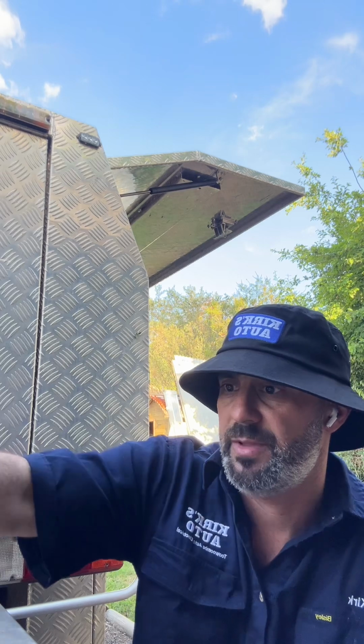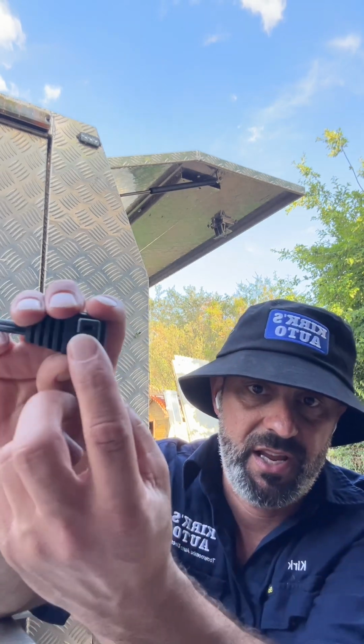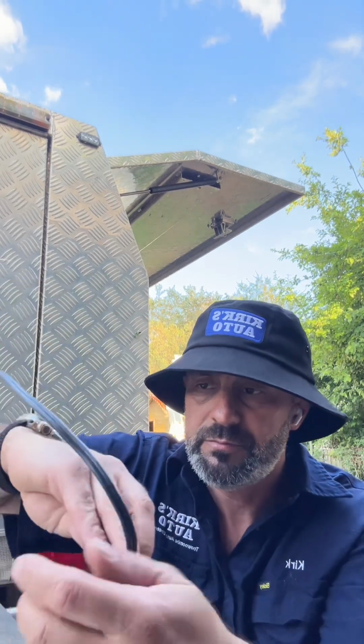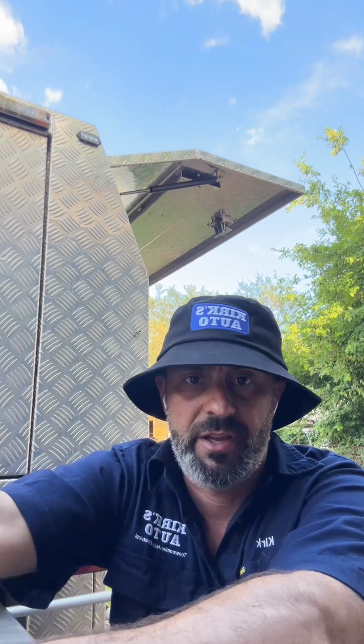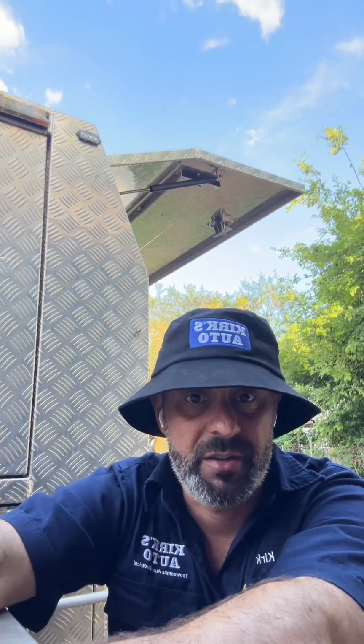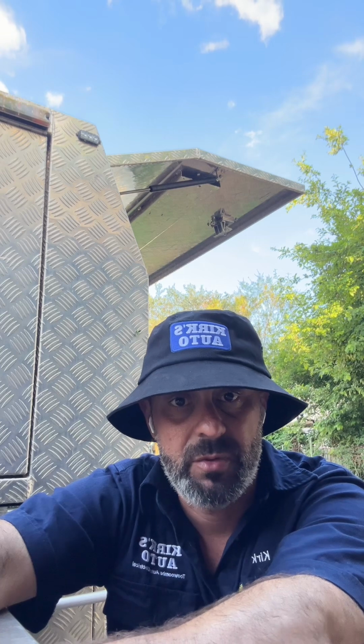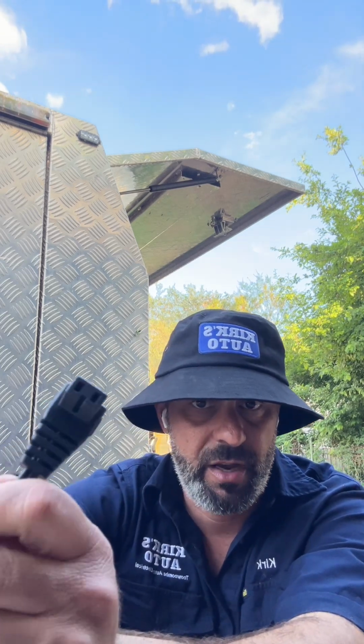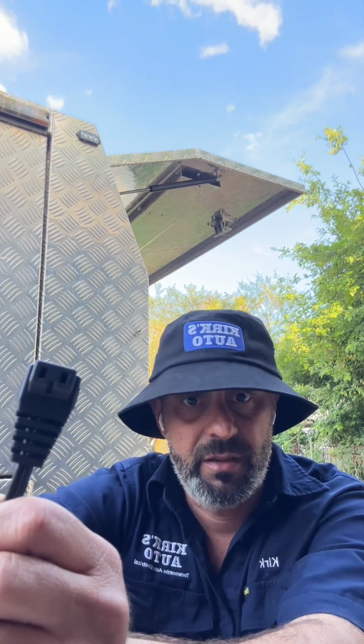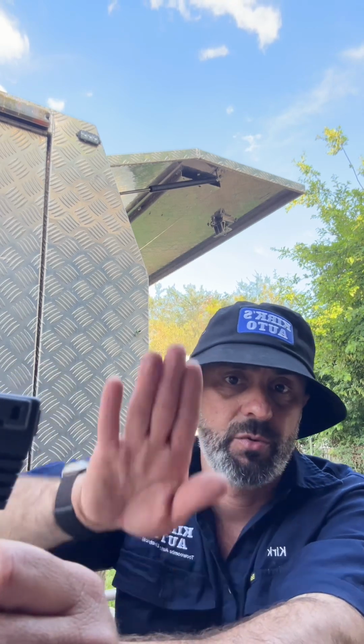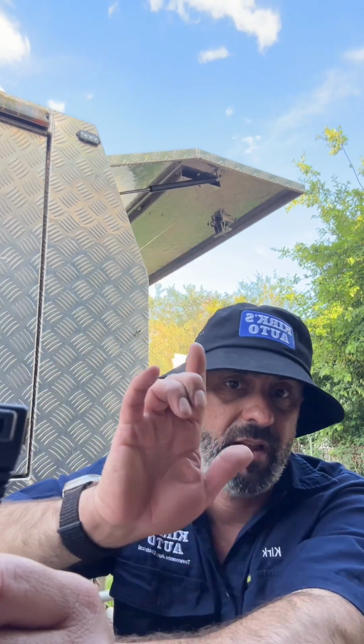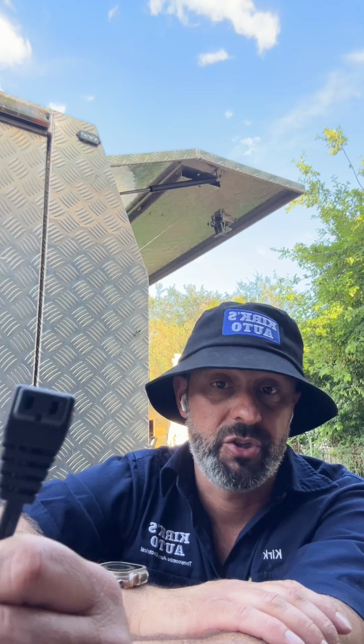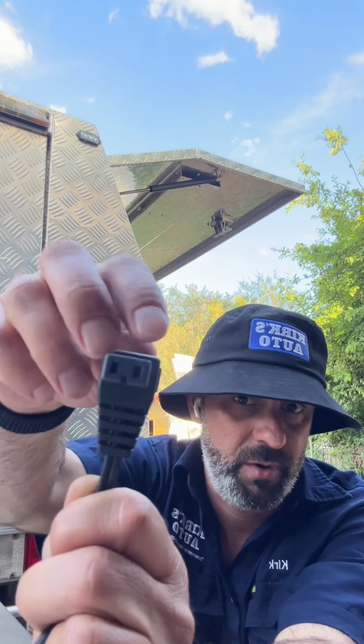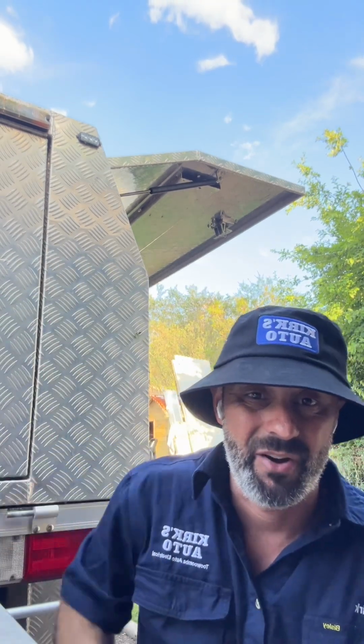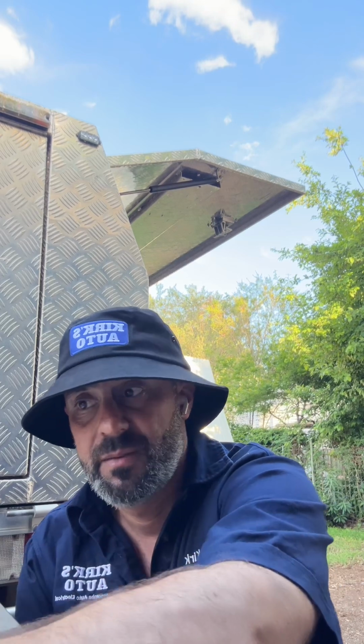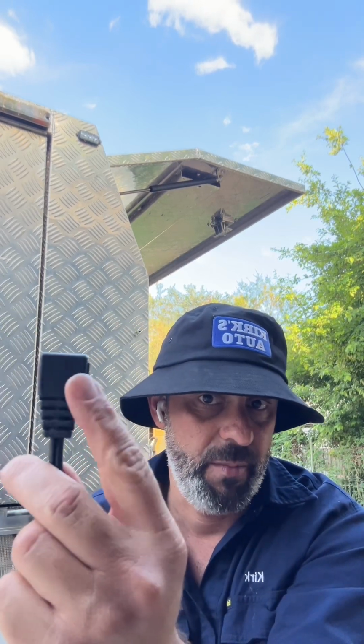Where the hot joints normally happen on these guys is actually inside here and onto your fridge. Those hot joints generally come from the cable also being undersized, too small, which creates a hotter joint. The lower the voltage goes, the amperage has to increase, and when you increase that amperage, you're going to get hotter joints. Wherever these little termination joints are, wherever these connections are, they're going to get hot, okay, and they're going to melt. So that's why you sometimes see these with a melted plug on the end of them.